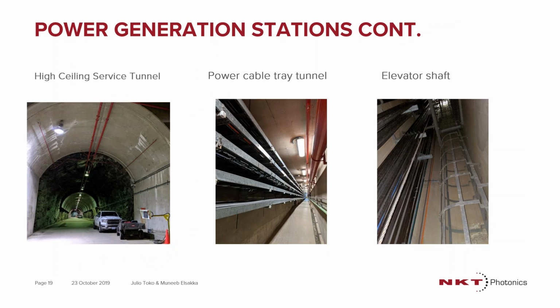These are some pictures illustrating this type of power generation station. You can have a tunnel leading to an area. You can have a cable tray, so you have power cable trays. One advantage for power cable trays is that, because this system is a distributed temperature sensor, you can also start doing dual approaches. So you can protect it for fire detection, but most importantly also prevent it.